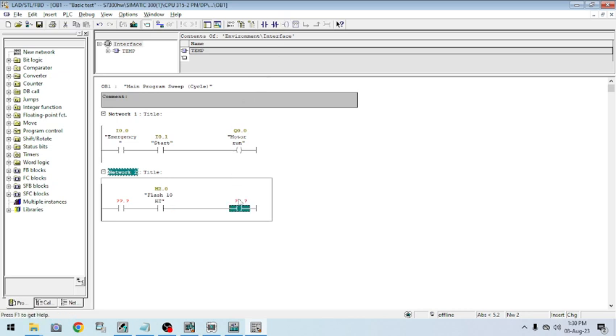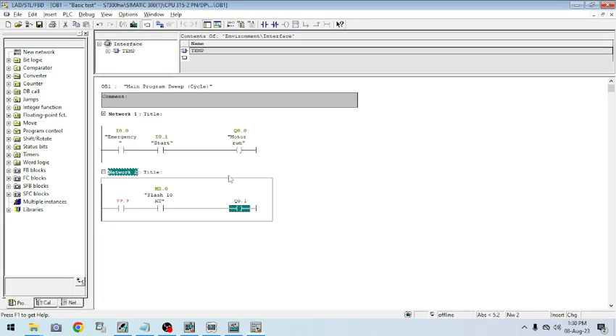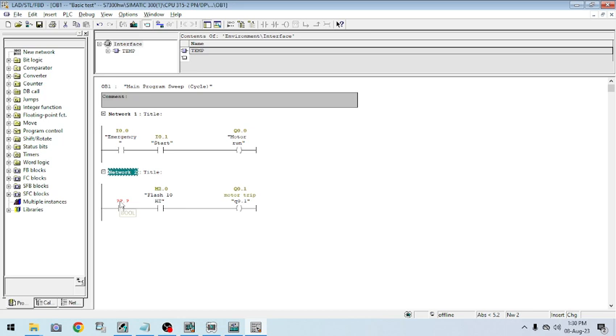In OB1, I am using a Normally Open contact and addressing it as M0.0 — using the symbol name for that clock bit. Then my output is Q0.1, which I label 'Motor Trip'. This way I am assigning the memory bit manually — I also assign I0.2 as an input.